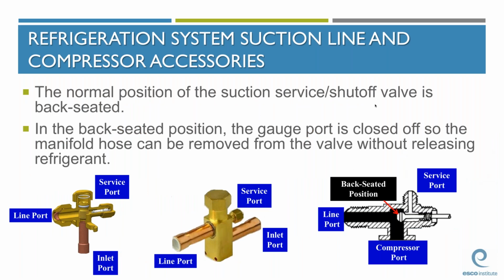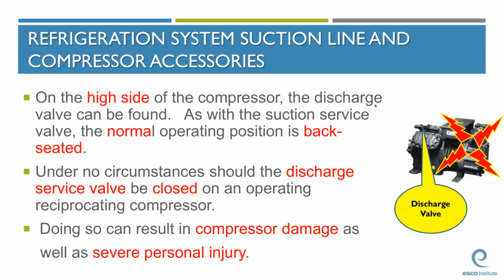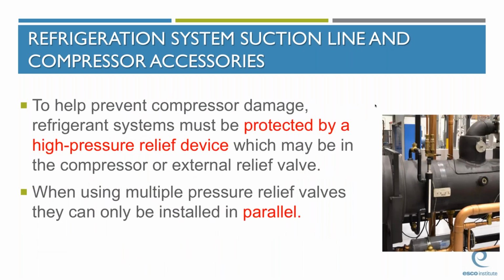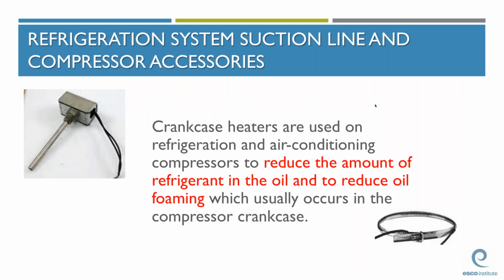To help prevent compressor damage, the refrigerant systems must be protected by a high pressure relief device. When a system is protected by multiple pressure relief valves, they're to be installed in parallel with each other. Pressure relief valves are never to be installed in series with each other. If we install them in series, what's going to happen is if the pressure builds up, that first valve is going to open, but now that's going to feed to the second valve, and that second valve is then going to have to open. So that's going to delay the response time or delay the relieving of pressure from the system. So relief valves are intended to protect the system from unsafe operating conditions.